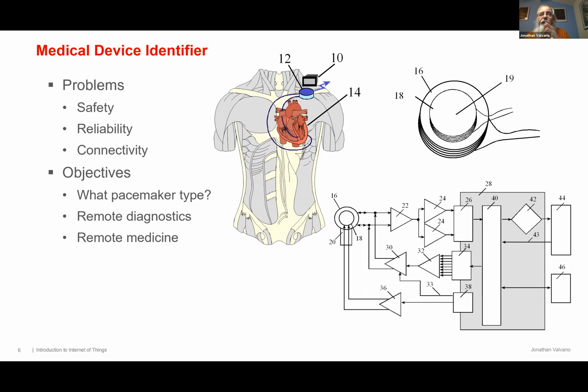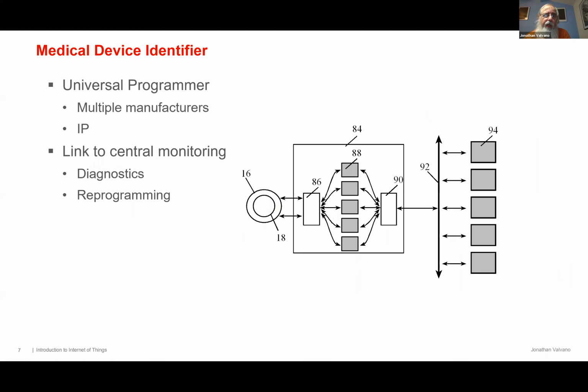And then again, that is a proprietary protocol communication. One of the features that we had in mind is if we could somehow, in a safe and protected way, embed each of the pacemaker companies' intellectual property into these little boxes here, and just connect our universal programmer to a secure internet connection.